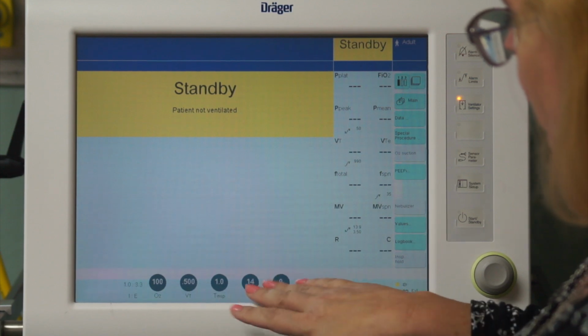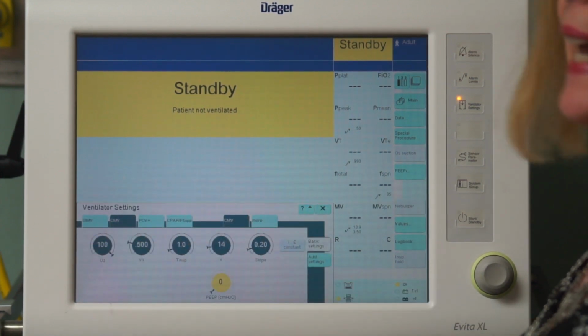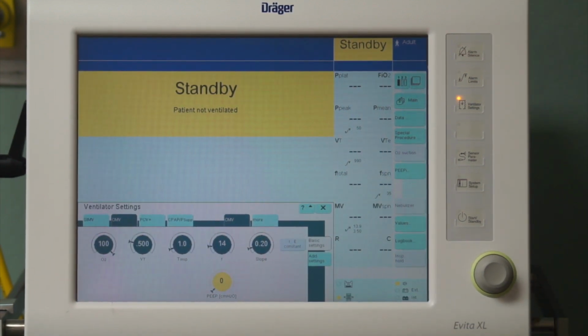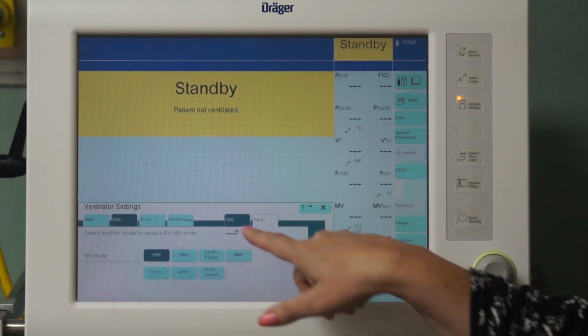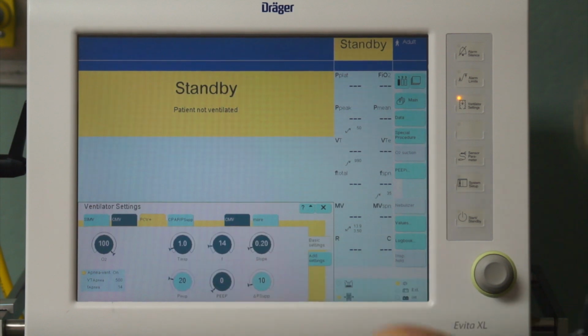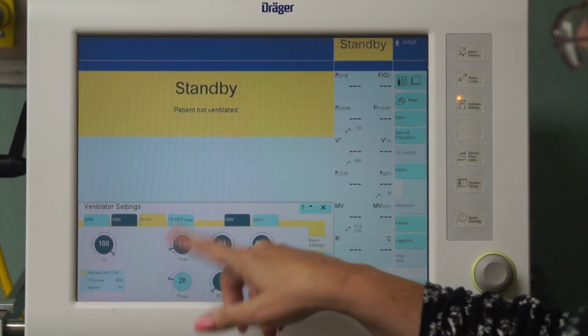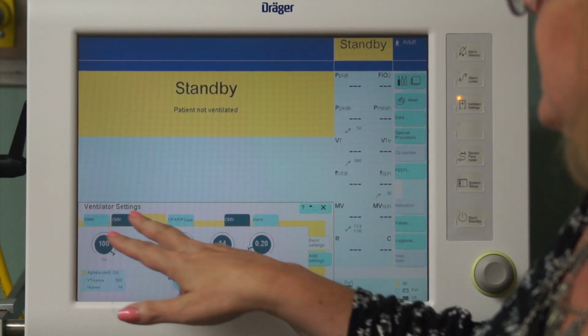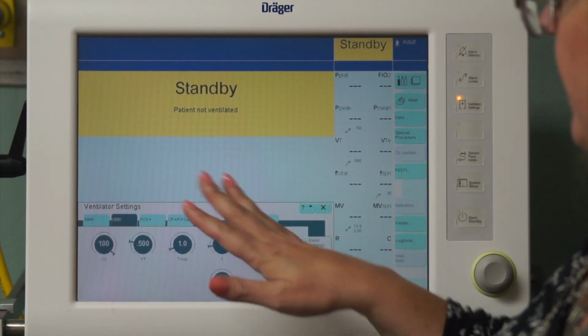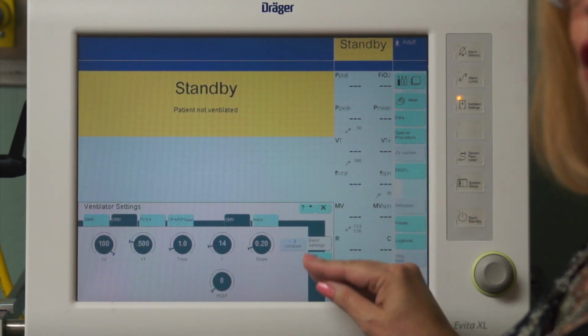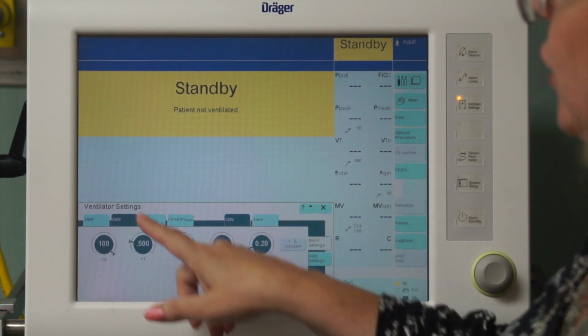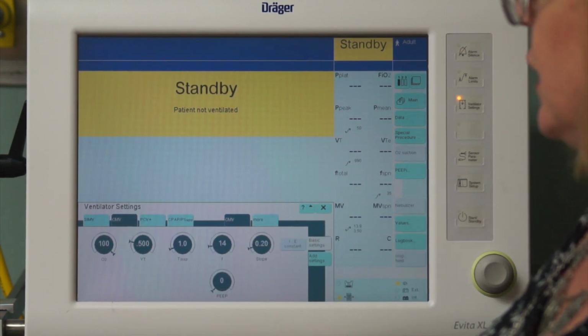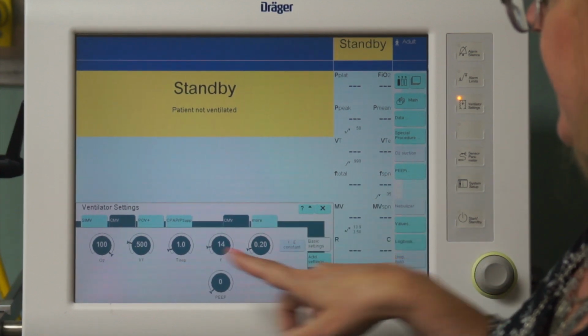Just by touching the screen down here, I'm opening up this tab system. So the Draeger kind of works on a tab system. If you touch the different tab, you'll get additional settings, kind of like an old index card system that you would have to look things up. So you need to touch what you're going to set it up on in order to get those additional settings. In this case, we're going to use CMV or assist control, and we're going to stay in volume.